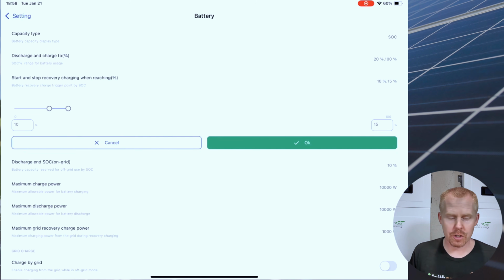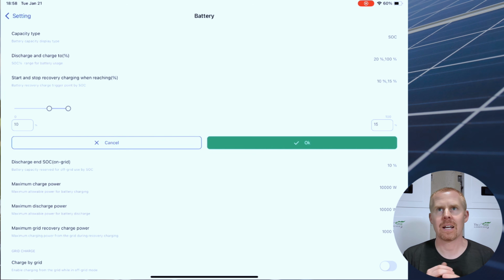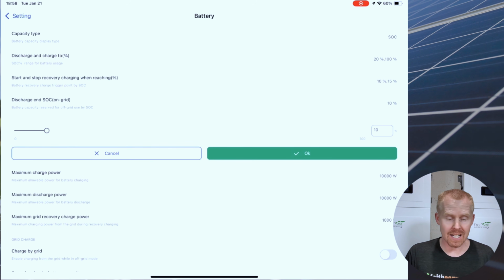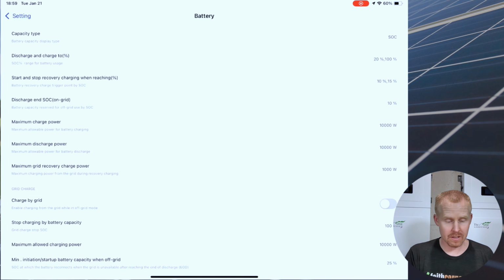A recovery charge is kind of like an emergency charge from the grid or from the generator, I believe, with the values that we have set right here. If they get down to 10%, it is going to try and charge from the grid or from the generator, whichever is available. It wants to keep your battery from getting too low. Discharge end, state of charge on grid, we saw that back in the user settings. Right here, it's set to 10%. These do mirror between the user settings and the installer settings.